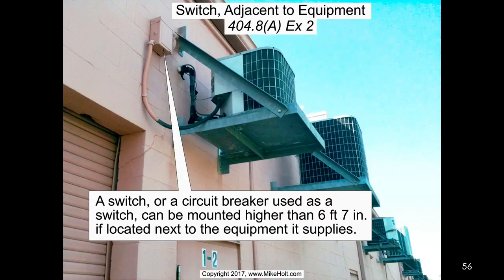Okay, now again, I'd rather this rule be contained. If this is air conditioning and refrigeration equipment, I'd like to have the rules on air conditioning and refrigeration, on the location of the disconnect, identify that it shall not be any higher than 6 foot 7 inches, except where it's located adjacent to the equipment that it's supplying. Then it belongs there. So this rule needs to be peppered where the rules belong, not be a general rule that then prohibits applications.